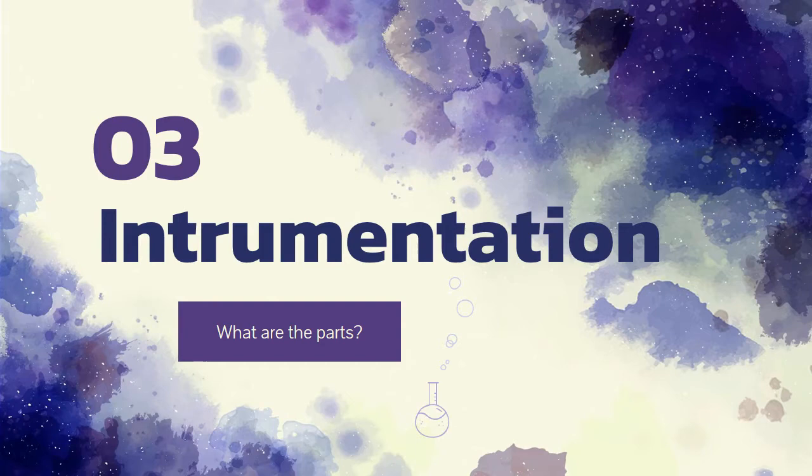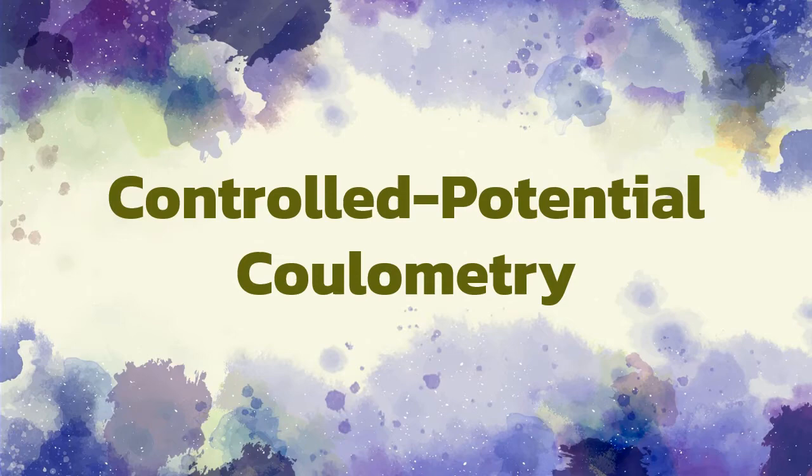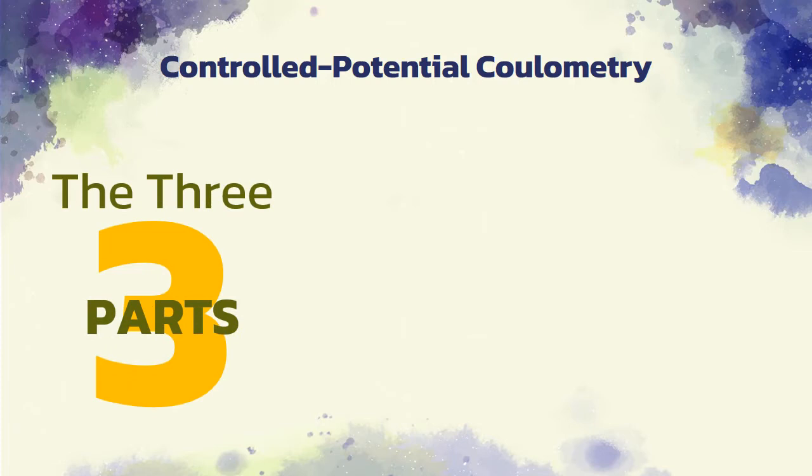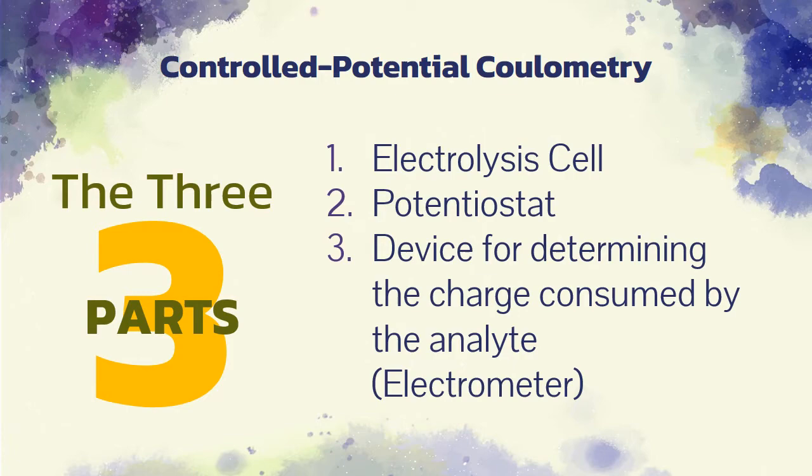Earlier, I have introduced two types of coulometric methods. I will be discussing the instrumentation behind each of those methods. Starting with controlled potential coulometry. The instrumentation for potentiostatic coulometry consists of an electrolysis cell, a potentiostat, and a device for determining the charge consumed by the analyte.